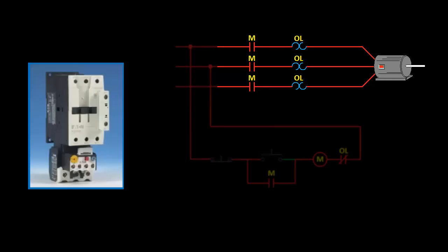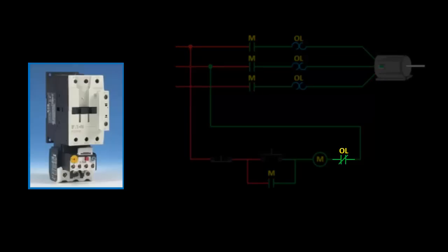The higher the current, the hotter the heating element is going to get. Once it reaches a certain temperature, it is designed to trip, opening up the normally closed contact, de-energizing the contactor coil, and opening up the contacts in the power circuit and shutting off the motor.